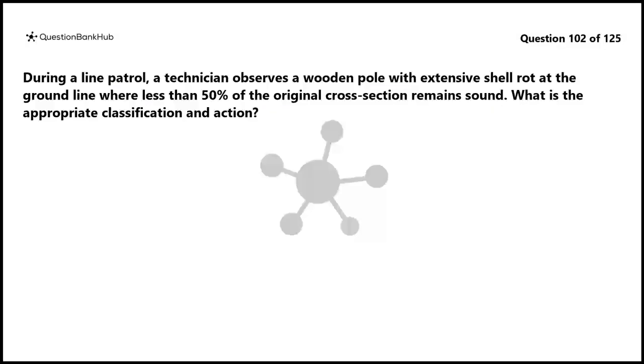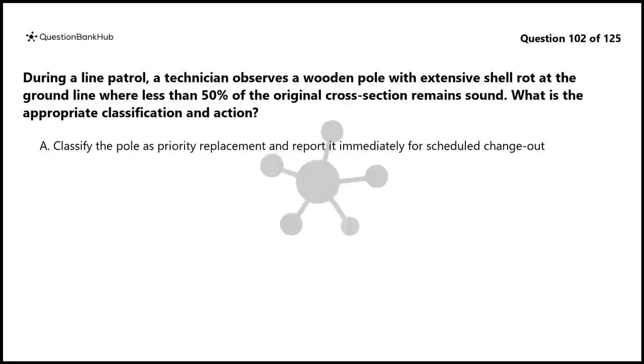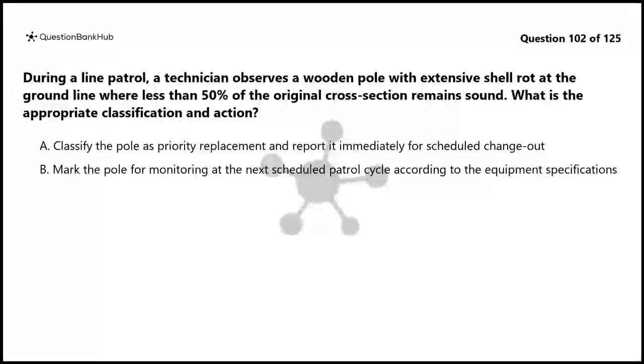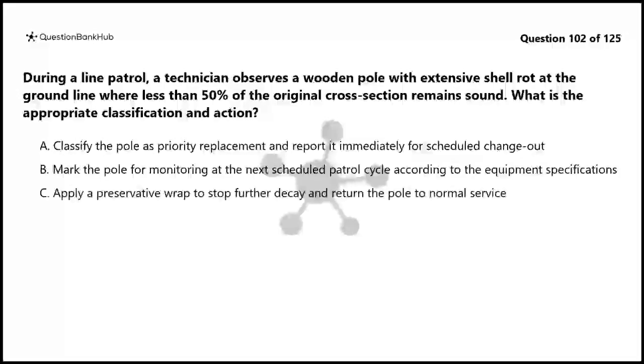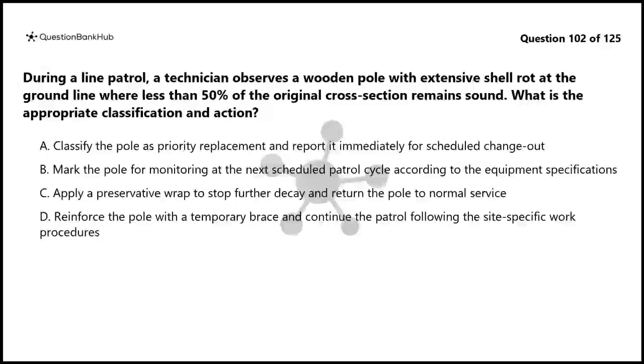Question 102. During a line patrol, a technician observes a wooden pole with extensive shell rot at the ground line where less than 50% of the original cross-section remains sound. What is the appropriate classification and action? A. Classify the pole as priority replacement and report it immediately for scheduled changeout. B. Mark the pole for monitoring at the next scheduled patrol cycle according to the equipment specifications. C. Apply a preservative wrap to stop further decay and return the pole to normal service. D. Reinforce the pole with a temporary brace and continue the patrol following the site-specific work procedures.